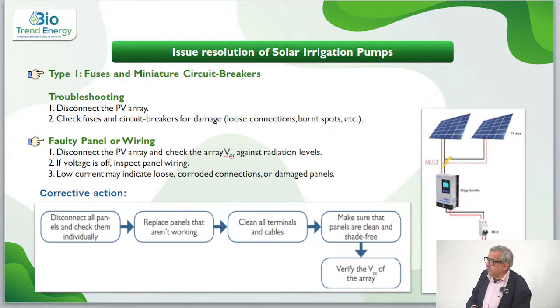Then second is a faulty panel or wiring, maybe some disconnection from the PV array, and check the array against radiation level. Because what happens is, on a non-sunny day output will be low. So radiation level and output voltage have to be checked all the time. Because if radiation is not there, voltage will not be there, for obvious reasons. But if radiation is there, output voltage needs to be correct.